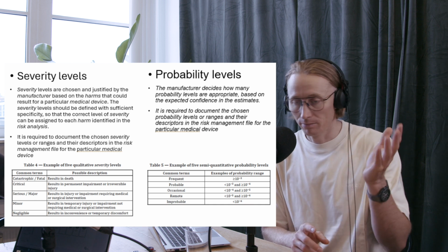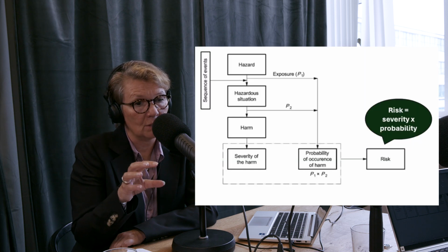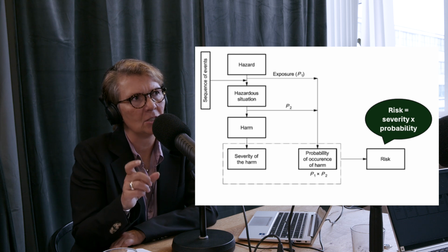You need to do it for each device you have. So a manufacturer having 20 devices would have 20 different risk management plans. When you look into the risk management standard, the number that we can't remember, these ratings, you can actually adapt. Also, I think it's important that it is you, the one who owns the device, who puts together the list of harms that can actually happen.